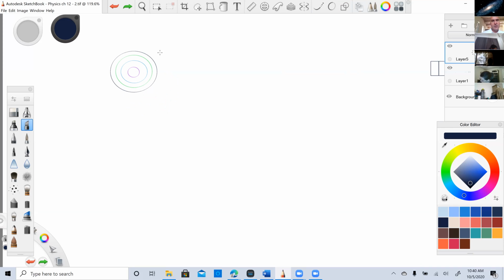So this image is looking straight down. You've turned the flashlight right at it, and you're looking at the bulb, right? This is looking straight at the transducer. You've pulled off the matching layer, and now instead of square or rectangular elements, you see 1, 2, 3, 4 elements. Each one separated a little bit, each one in its own individual channel. So each one of these has a single wire to it, but only 4. There's only 4 channels and there are 4 elements.